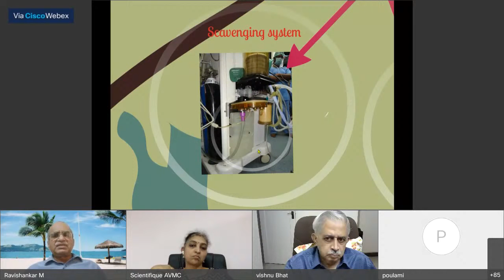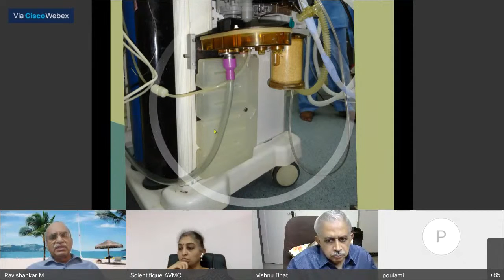Again, whatever gas that is spilling out in the OT atmosphere is better to scavenge out. So the machines that are there are using this scavenging port so that whatever is coming out in the breathing system gets accumulated, and finally they go out. This is active scavenging, so that a little bit of suction power is applied, and whatever gas spills out is sucked out and then put into the atmosphere at a higher level so that it does not pollute the operation theater. But whatever is coming out there is definitely going into the atmosphere.